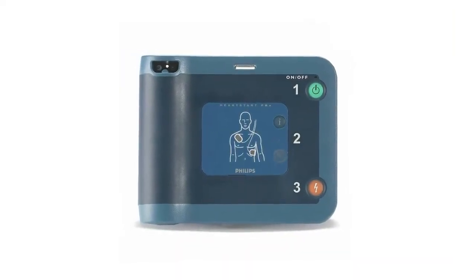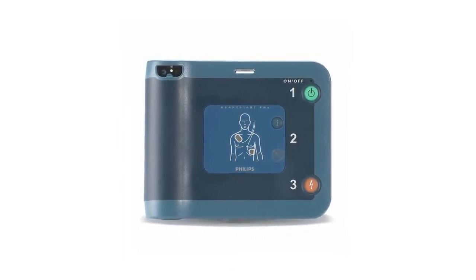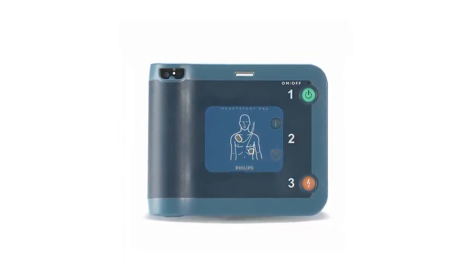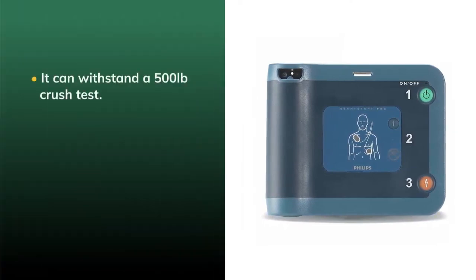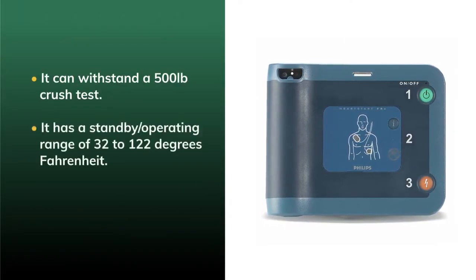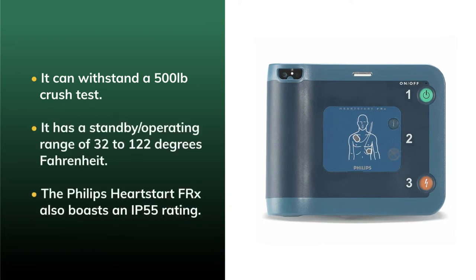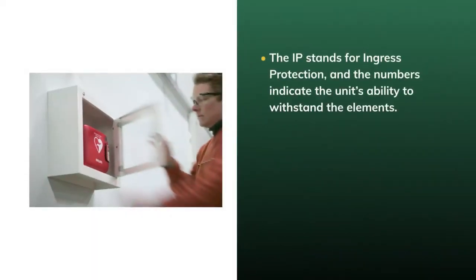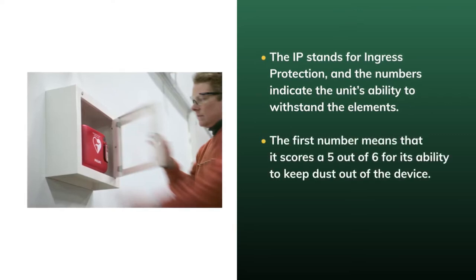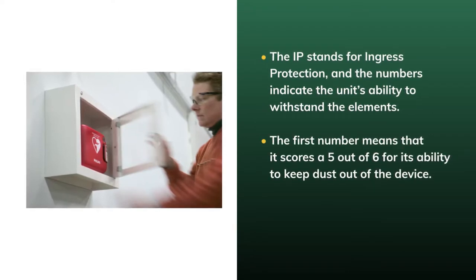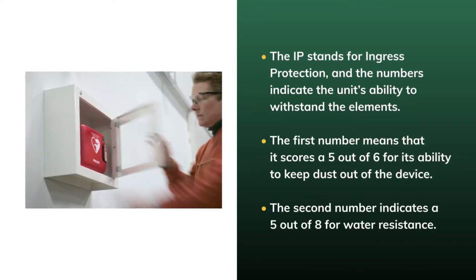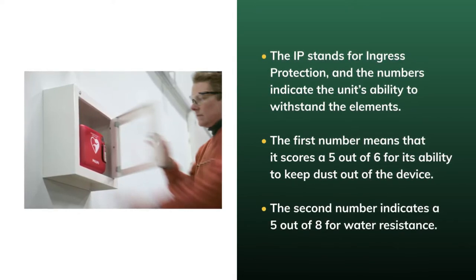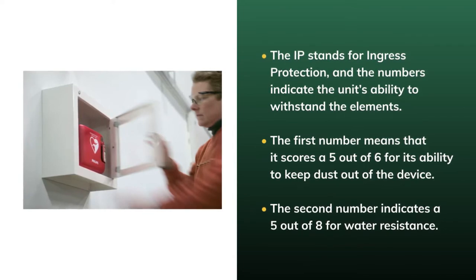The Philips HeartStart FRx is not your ordinary AED. It's a tough, durable unit meant for use outside of home, office, or school situations. It can withstand a 500-pound crush test and also has a standby operating range of 32 to 122 degrees Fahrenheit. The Philips HeartStart FRx also boasts an IP55 rating. The IP stands for Ingress Protection, and the numbers indicate the unit's ability to withstand the elements. The first number means that it scores a 5 out of 6 for its ability to keep dust out of the device, and the second number indicates a 5 out of 8 for water resistance. Currently, this rating is the highest you can find for a commercially available AED.